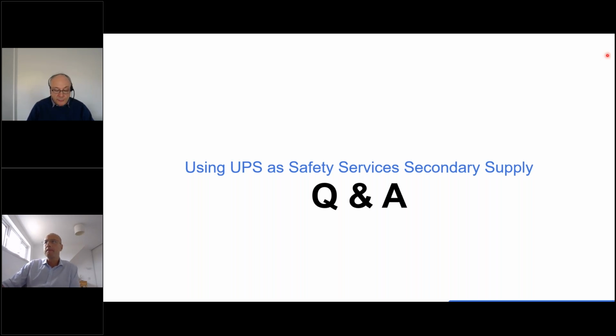Somebody else has asked, does it matter what battery is used for life safety UPSs, and are there any specific battery features to look out for? For a lot of life safety, no, but guidance tends to look at the valve regulated lead acid, which is a well suited battery. We've got people looking at lithium because they're smaller, but they tend not to be smaller on long autonomies. So lead acid tends to be the battery of choice, especially the valve regulated, because it needs less maintenance. And if we're in a healthcare environment for those critical supplies, and we have the HTM to look at, there are specific requirements that a battery has to be flame retardant, it suggests a 10-year battery, and it must have screw insert threads for the terminals. So there are different regulations for different types.